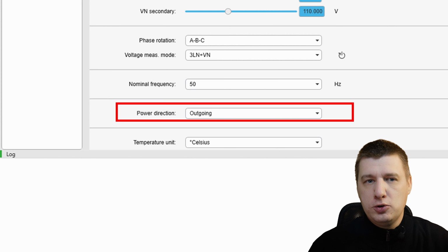Why bother with this? Firstly, it ensures your metering makes sense. You don't want your HMI showing negative kilowatts during normal operation. Second, it is vital for directional power protection. The relay needs the baseline to determine if the fault is forward or reverse. The golden rule is to match the relay settings to the physical role of the feeder. If it brings power in, set it to incoming. If it sends power out, set it to outgoing. As always, you should check your phasor diagrams.